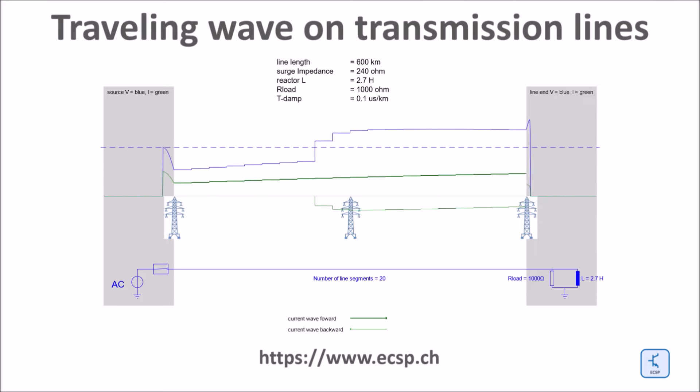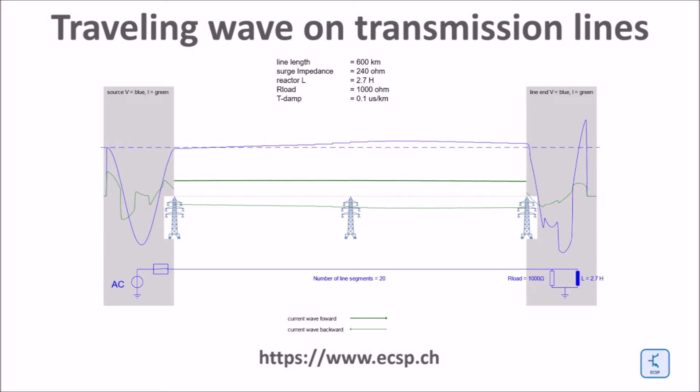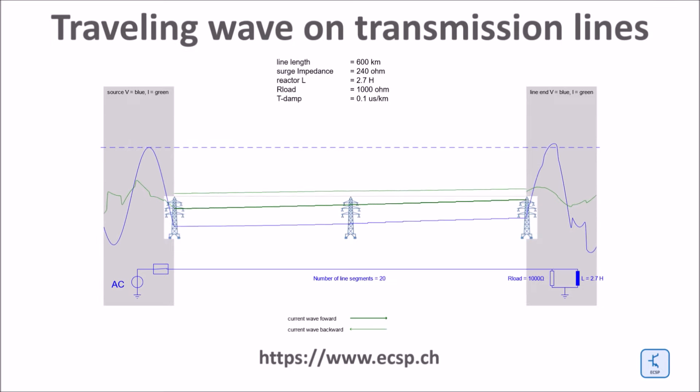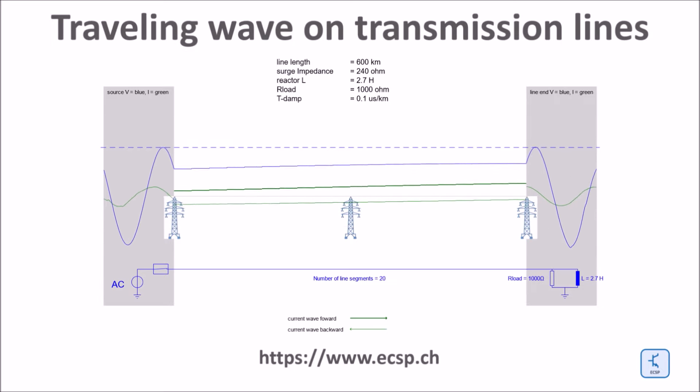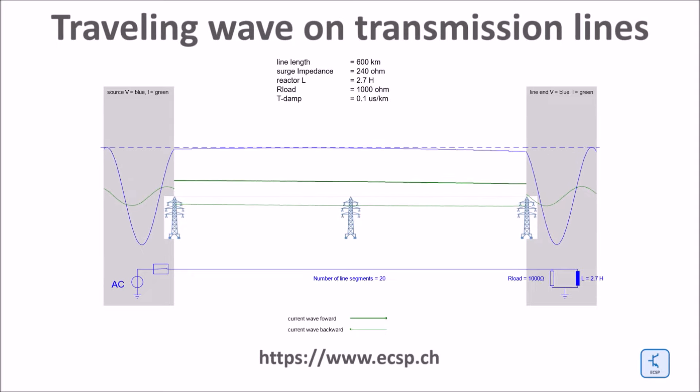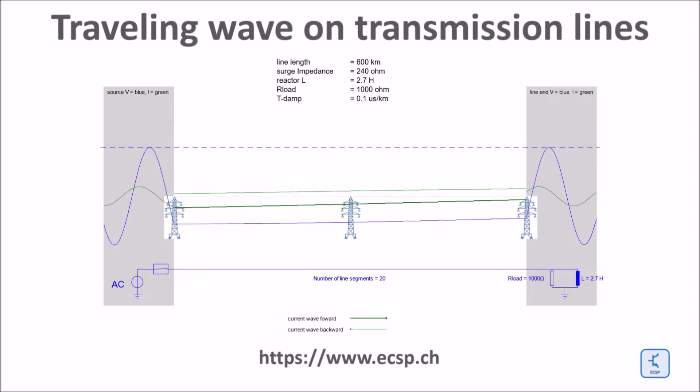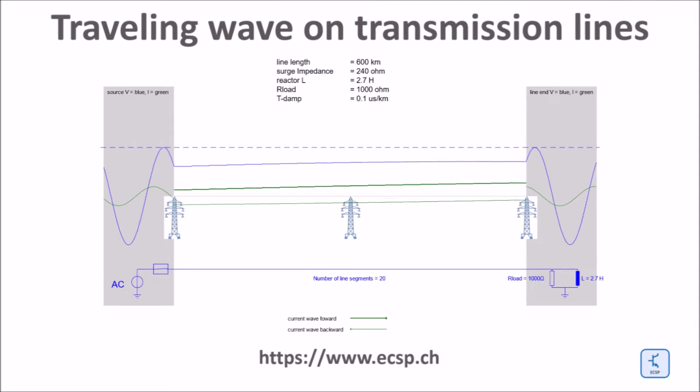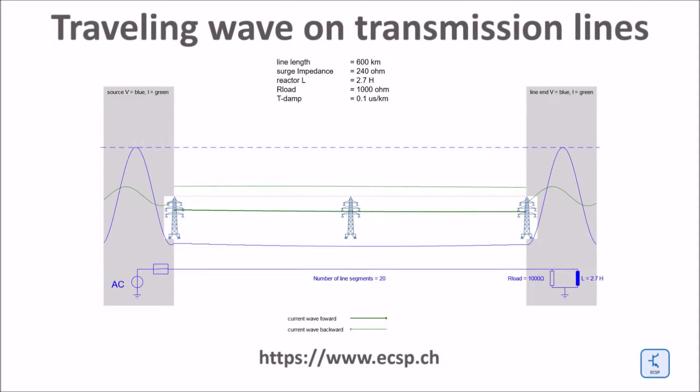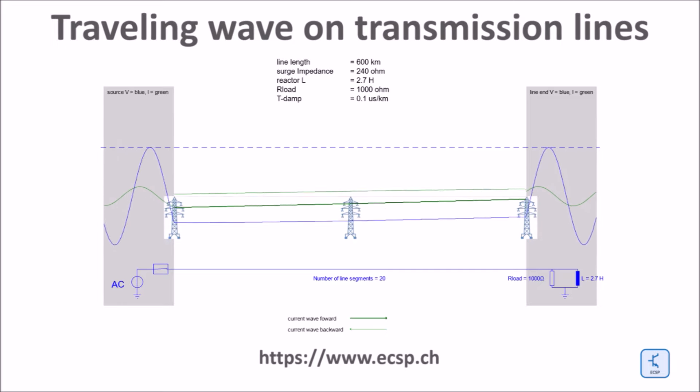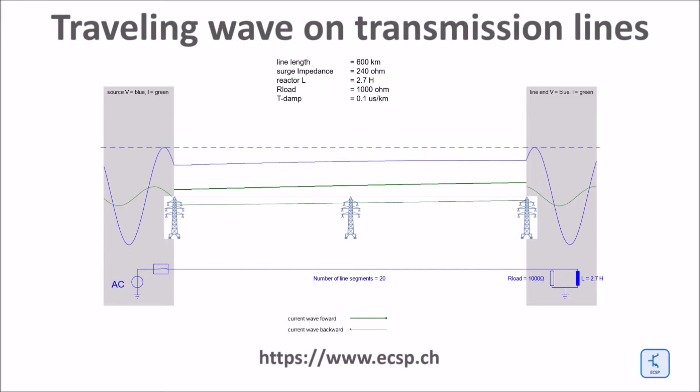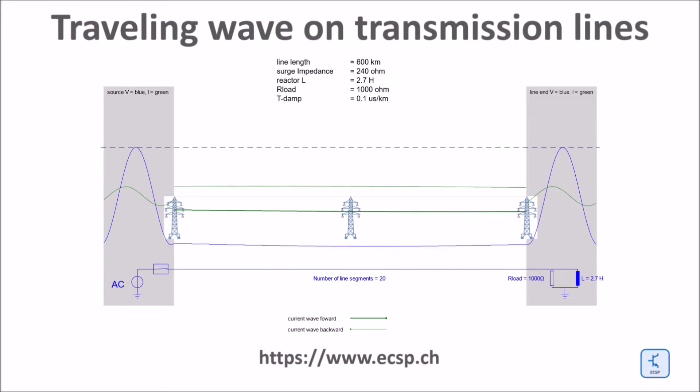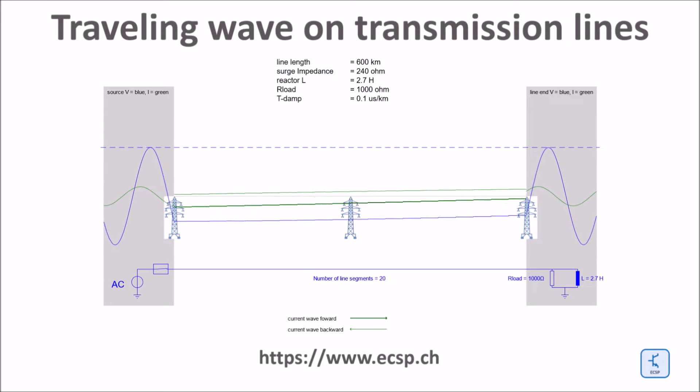Therefore in this case, the reactor would be needed at the end of the line as well, but for a lower reactive power rating. This means the reactor would get a higher inductance value. The needed reactive power compensation of a line has to be optimized by the operator. In some cases, even complex variable reactors have to be provided.